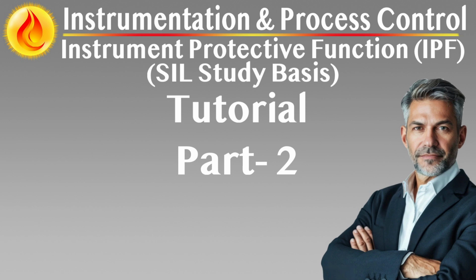Low: localized equipment damage, short interruption. Example: minor pump damage, piping stress requiring inspection and recommissioning. Moderate: damage to major equipment, several hours to days of downtime. Example: compressor failure, distillation column upset, raw material reprocessing. High: significant asset damage, prolonged unit outage or replacement. Example: fired heater, reactor, or major rotating machinery loss.